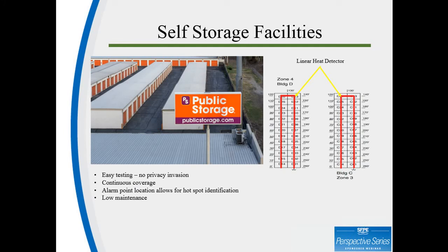Self-storage facilities demonstrate the versatility of digital linear heat detection. Running the detector above each unit allows for zero privacy invasion when the annual testing and commissioning is performed. By shorting the detector at the end of the line, you can be assured it is operational everywhere along its length. Further, if these facilities are not temperature controlled, the detector is immune to rapid temperature changes. Finally, if or when there is a fire, the alarm point location will tell first responders or owners exactly which units are experiencing the overheat.